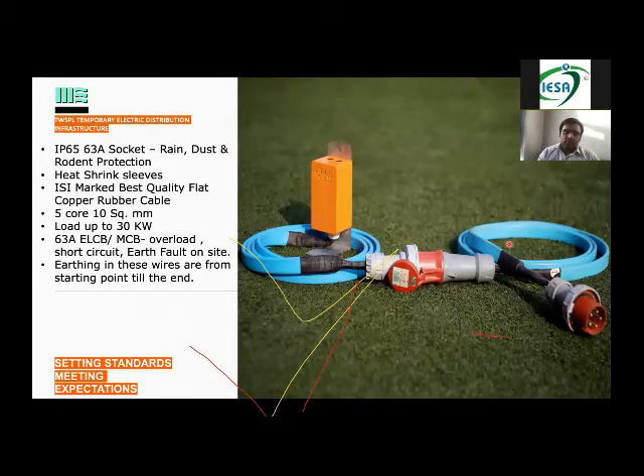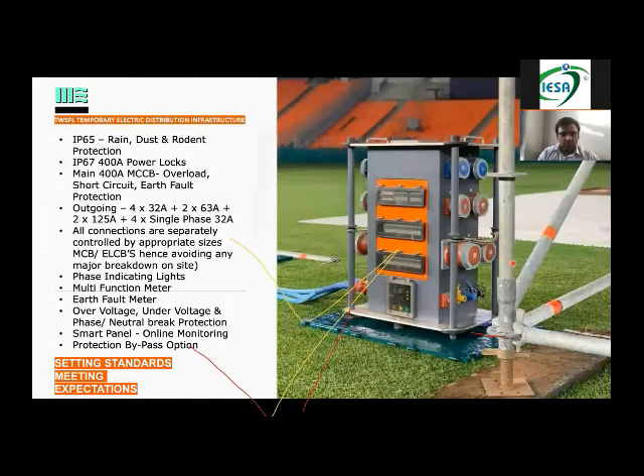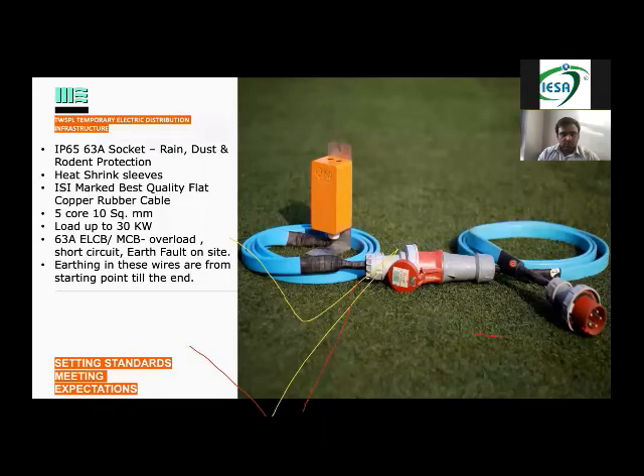Again, a different type of socket. This is for 30 kilowatts. Again, like we've differentiated our boxes, it is orange color. So this is 30 kilowatts, 10 square mm wire, 63 amps ELCB or MCB with a heat shrink sleeve. So again, this goes inside the panel, separately controlled. So anybody who's asking for a 30 kilowatt load, that could be your 17-ton AC on site, or that could be an exhibitor who's asking for 30 kilowatts load.